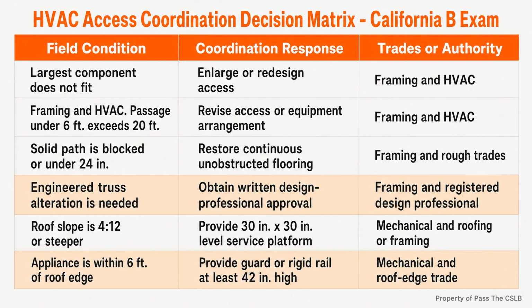The decision matrix shows the stop points. If the largest component does not fit, enlarge or redesign the access. If a low passage exceeds 20 feet, revise the equipment or access arrangement. If the path is blocked, restore a continuous, unobstructed route. If engineered truss work is affected, stop for written design professional approval. If roof edge or roof slope conditions trigger protection, provide the required platform or guard.